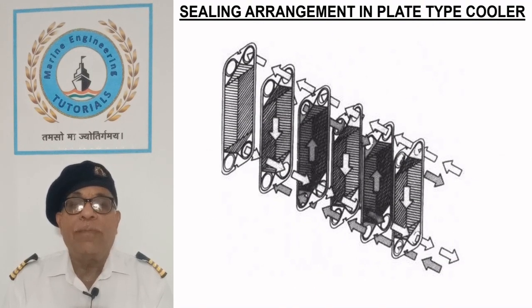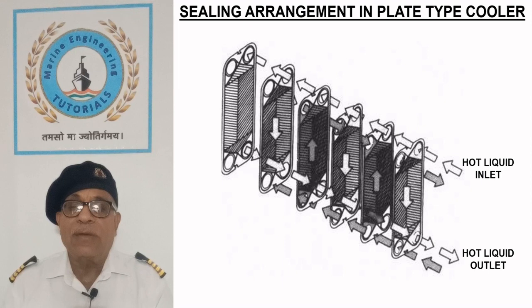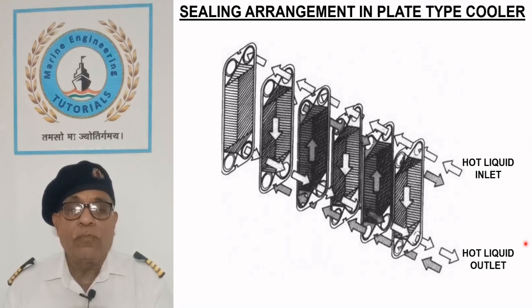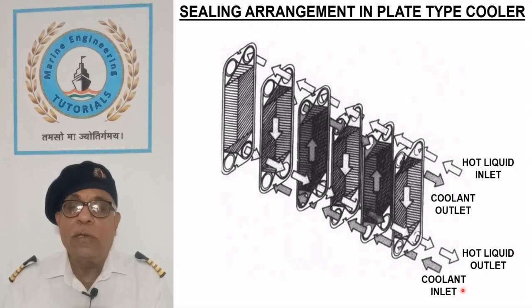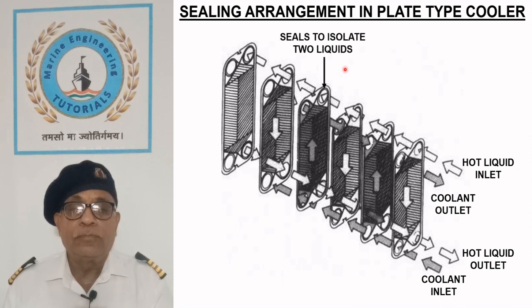Sealing arrangement in plate type coolers. The sketch shows the flow of two liquids taking place between the plates and the method of sealing between them. We can see that hot liquid enters from the top in alternate plates and flows downwards through the corrugations and leaves from the bottom. Similarly, the coolant enters from the bottom and passes through the other set of alternate plates and leaves from the top. Seals are so arranged that one fluid flows in alternate passages between the plates in the opposite direction.